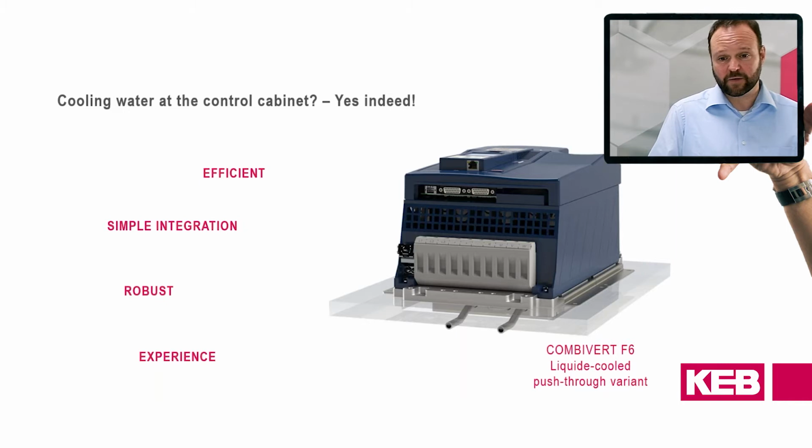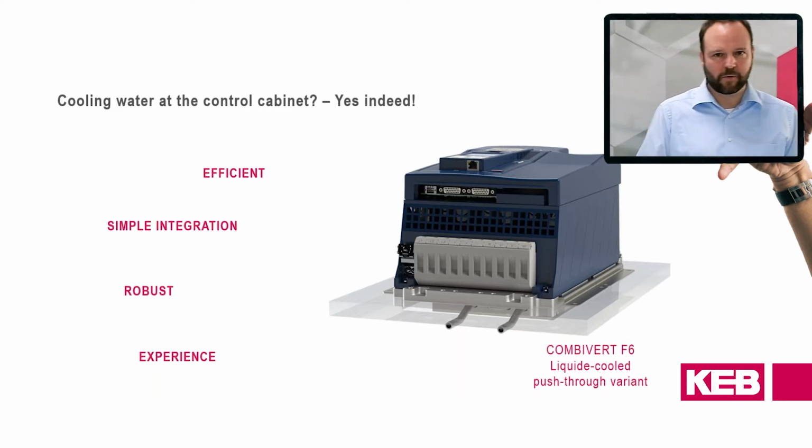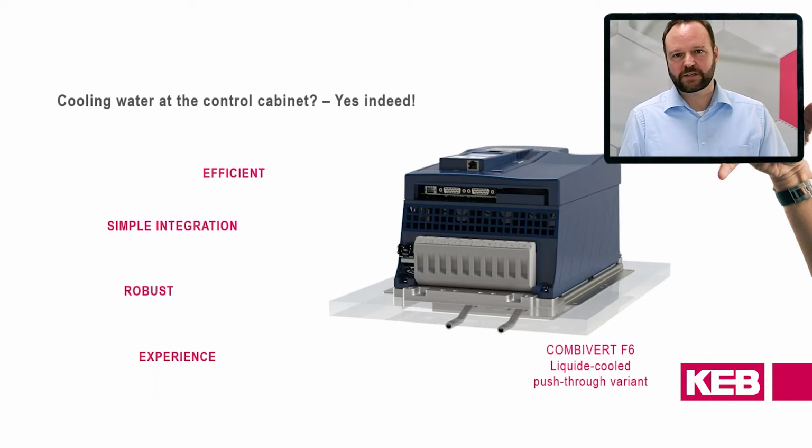So talking about the cooling water, this is a third generation of inverters with water cooling we supply. So we have an experience for almost 25 years now with this technology. Cooling water itself is a very effective cooling. So the dimensioning of the cabinet can be made smaller because less heat disappears into the cabinet.